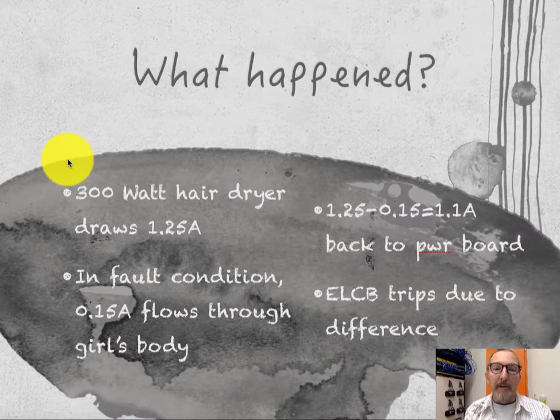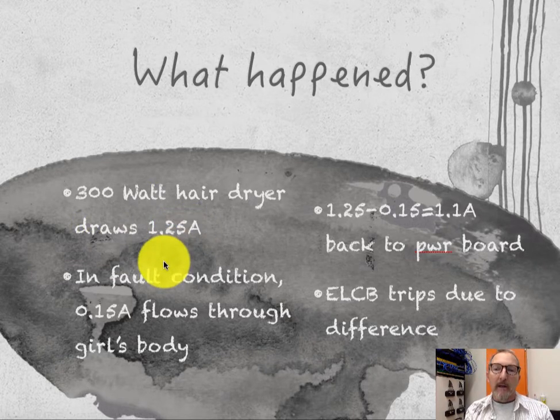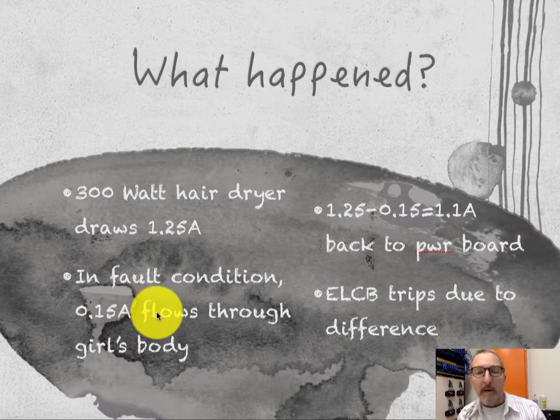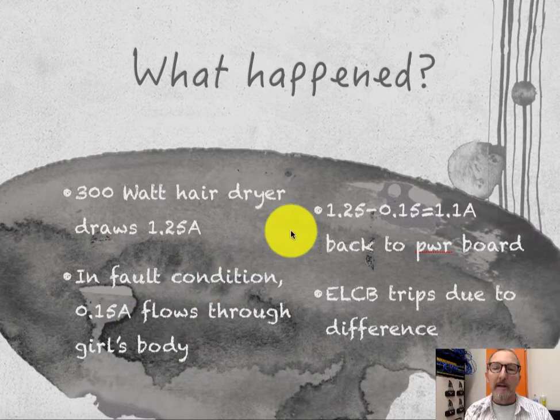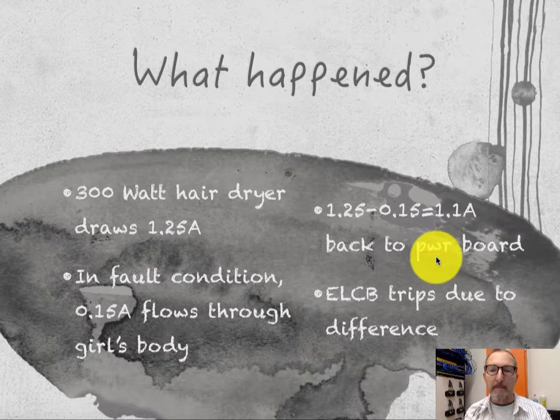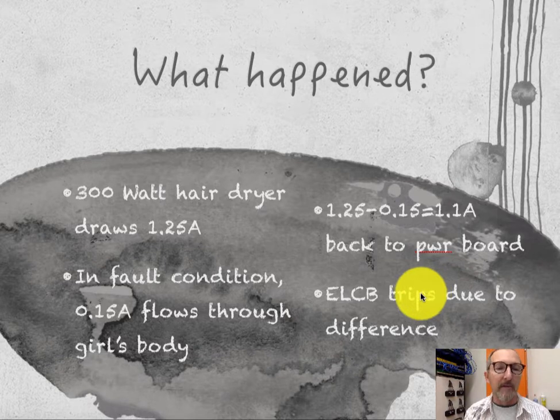Summary of what happened: 300-watt hair dryer normally drawing 1.25 amps. In a fault condition, 150 milliamps — 0.15 amps — of current flows back through the girl's body to ground. 1.25 amps minus 0.15 amps leaves 1.1 amps going back to the board. The ELCB sees that difference and trips.